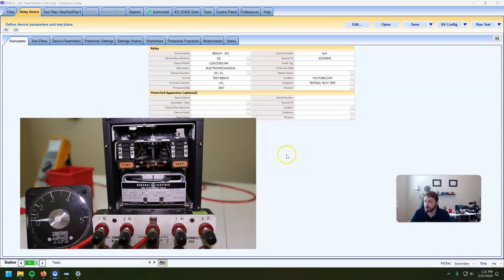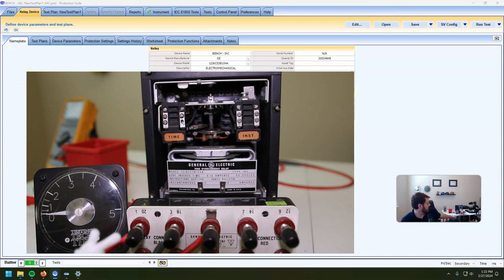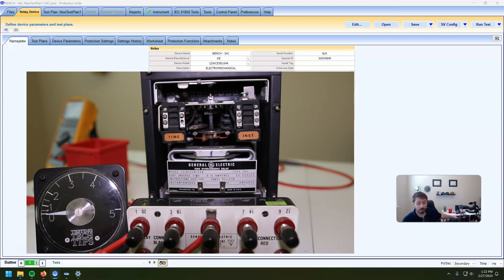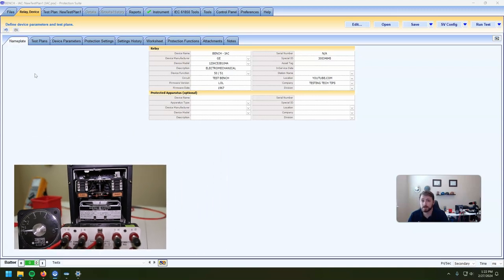In Protection Suite, we're going to get this set up with as much nameplate information as we can. I've got terminals 1 and 2 — those are my time over current trip terminals. So when the time over current dial closes, that's what's actually going to trip. And I'm hooked up on my CT inputs 5 and 6 from my test set.